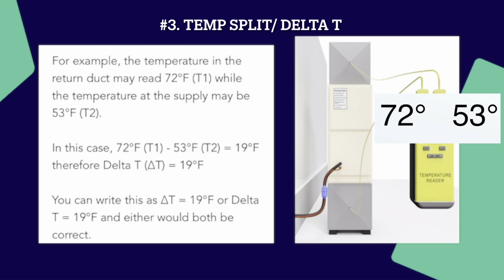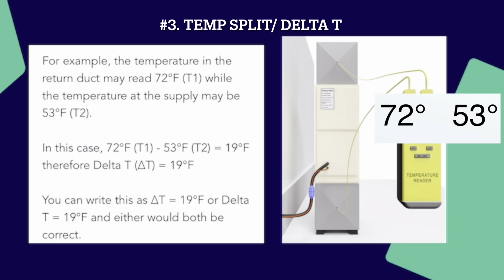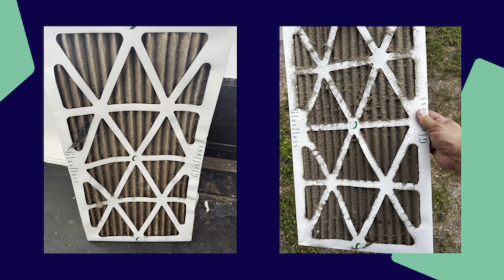Step number 3 is temperature split, or delta T. This is very, very, very important in air conditioning. You're typically looking for a temperature split between 16 and 20 degrees. The temperature split can be found by taking the return air temperature and subtracting the supply air temperature from it. If you're not within that range, the next thing to check is number 4. Check the filter. It's very important.